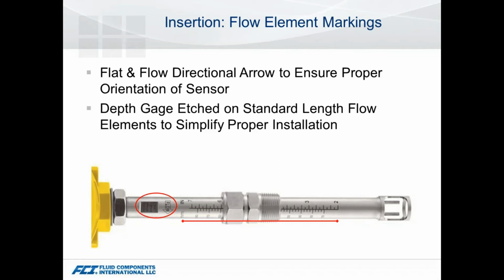So we etch this depth gauge onto it, and by taking the proper measurements of your piping, your process connection and such, you can help insert that insertion style meter to the point where it's either a 1/2 inch or 1/4 inch beyond center line, depending upon the product.